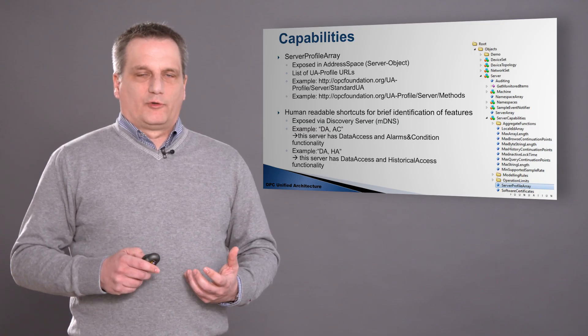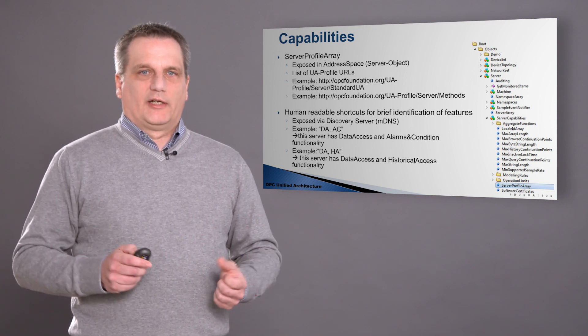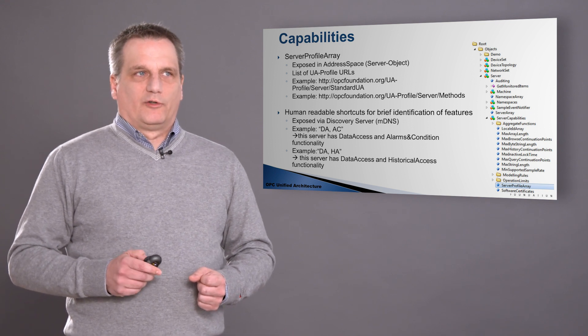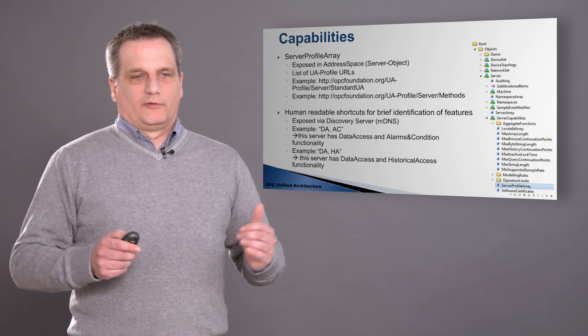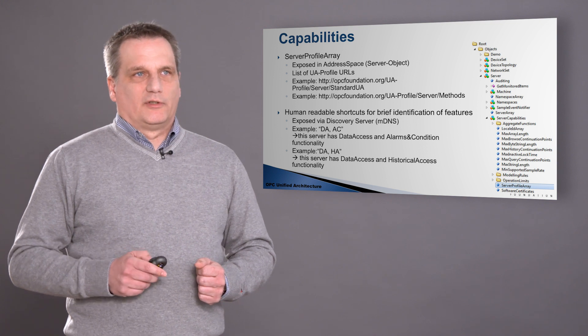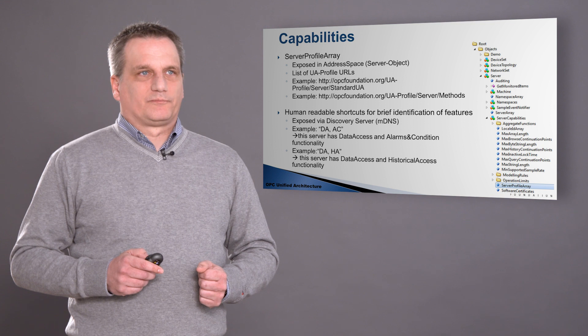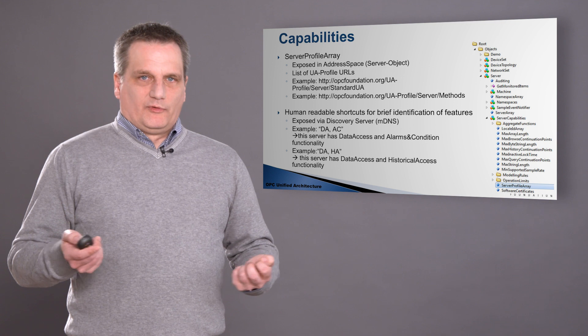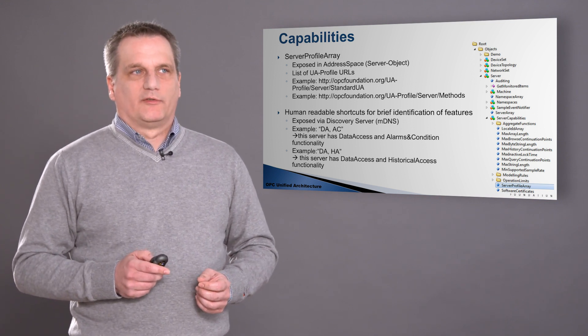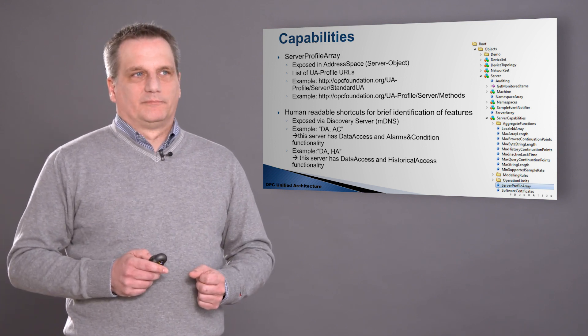Any OPC server should expose its capabilities so that the receiver can adapt to that. To do so, there is an object inside the server address space called the server profile array, and in this array you can find all the profiles that this server supports. You can see it here from the picture on the right side — the tree of the address space where you can find it. In addition to the profile URIs, we have human readable shortcuts which give you a very brief summary of capabilities, and these are also discoverable and exposed through the discovery service. For example, DA means data access, AC means alarms and conditions, and HA means access to historical information.